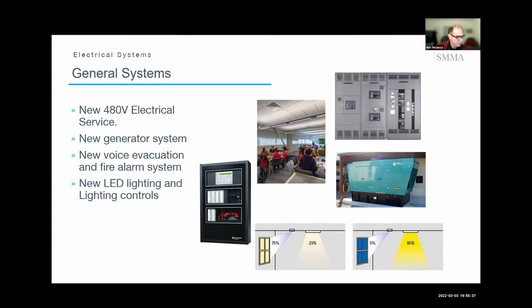For the electrical systems, there's not as much complication in the choices, but the building will have a new 480 volt, 277 volt electrical system, and a new generator system. The generator system is an area where there's often discussion. We did get feedback from the focus groups that they wanted us to look into natural gas. Normally in a building we would do a diesel generator system because the code requires an uninterruptible power source, and they don't consider natural gas uninterruptible unless it's acceptable by the code officials. But because there was some interest from the focus groups in that, we may explore it. That's one area of discussion. The other area of discussion in the generator systems is what to put on it. As a minimum, we usually put all the emergency lighting.